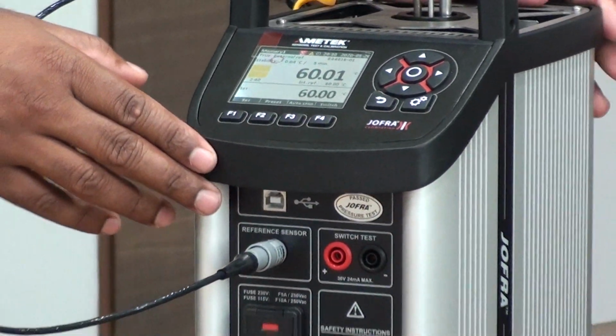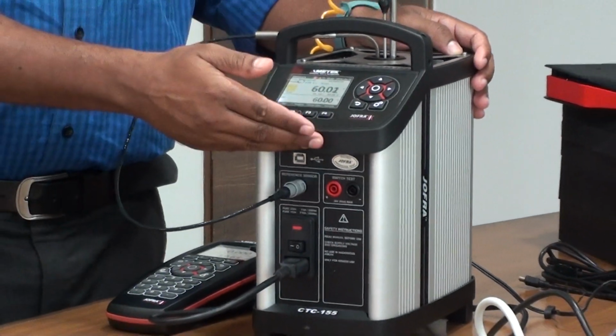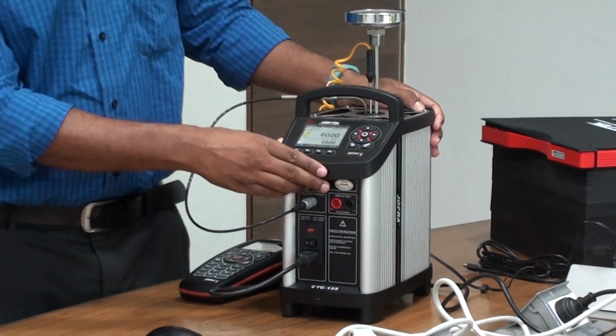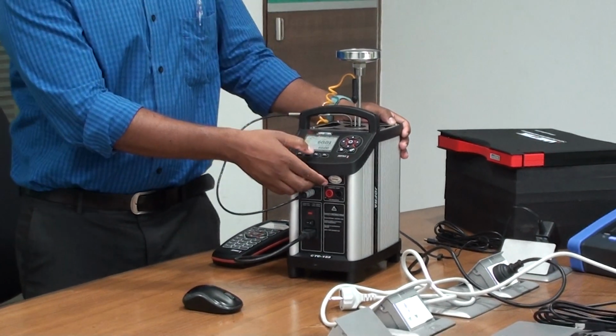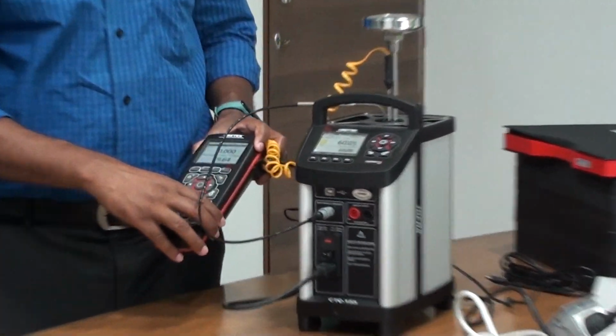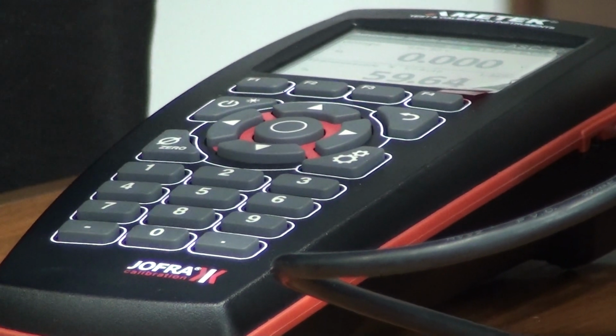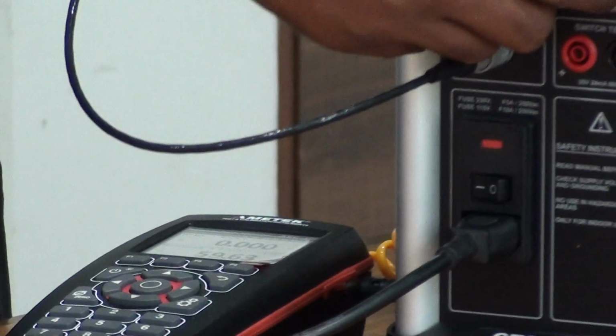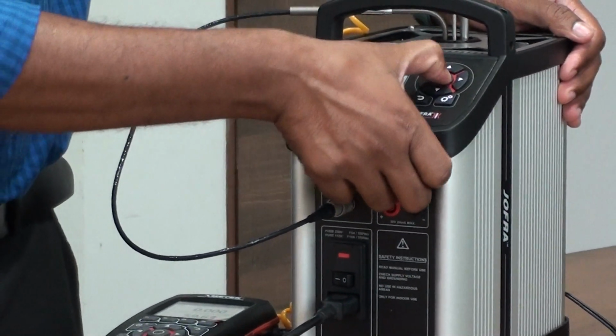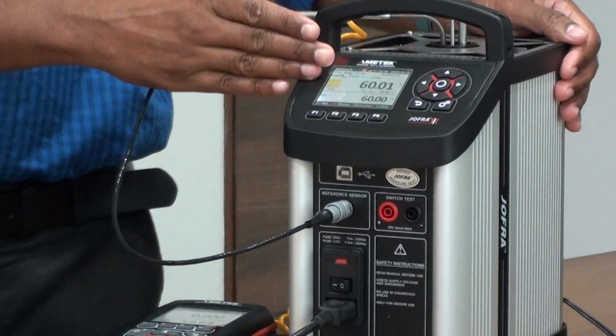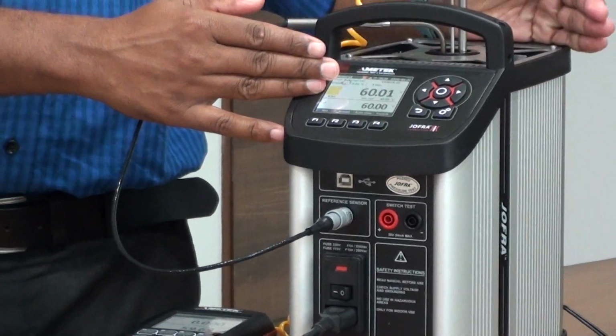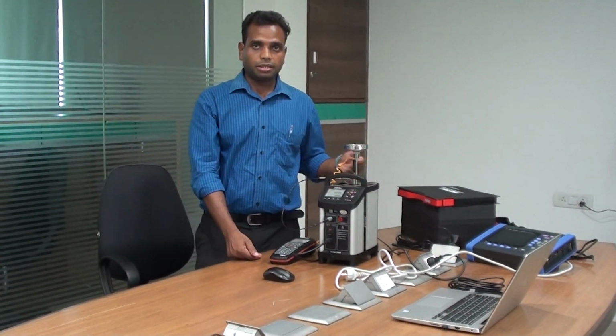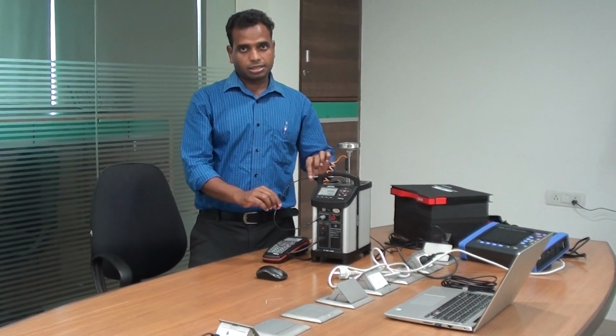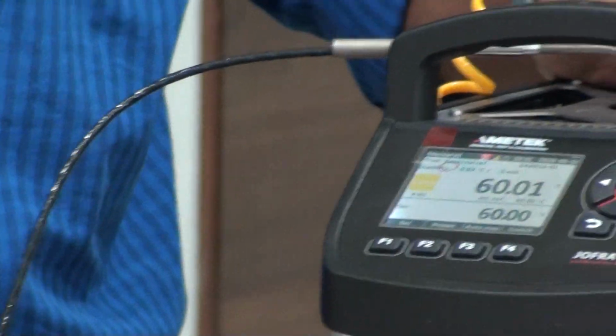Now we'll start 2-3 steps of calibration. First we will set the temperature at 60 degree, and then we will take the reading with the ASC 400, which we have for device under test reading. So I am setting up the 60 degree temperature. Now the temperature is set at 60 degree. We'll see what time it takes and what deviation comes out between the DUT and the master sensor.